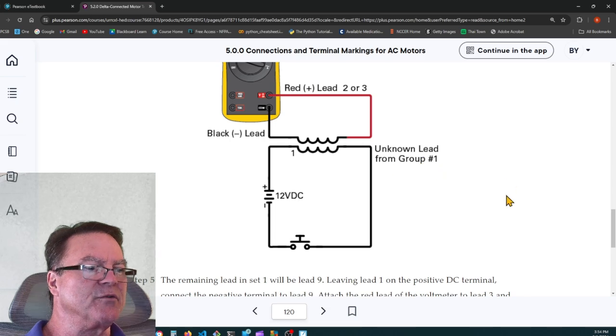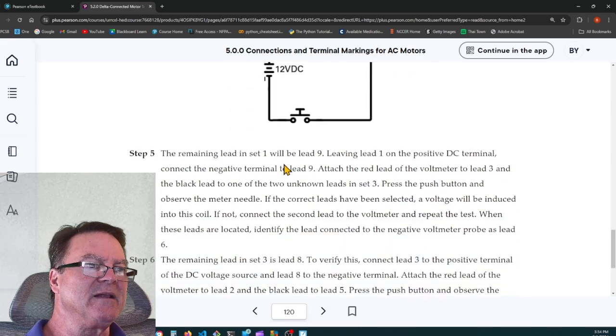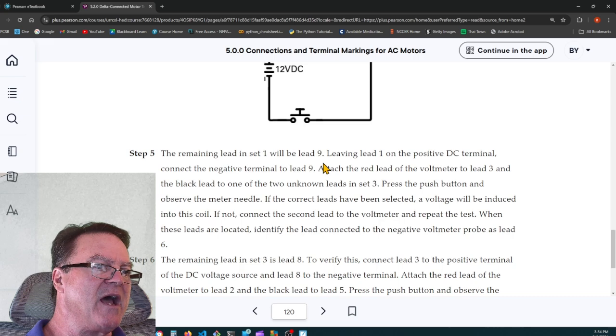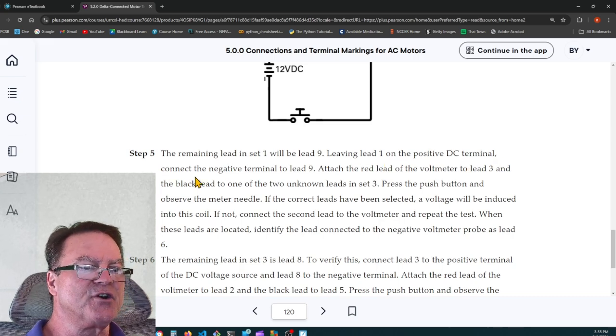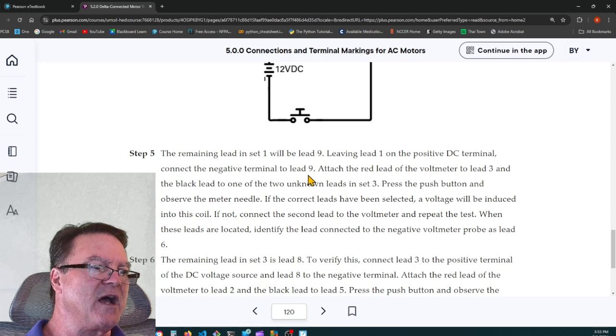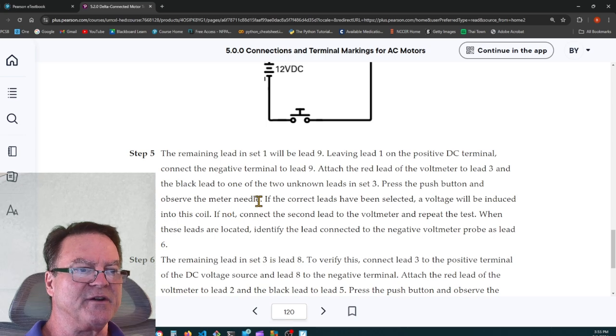This is the unknown lead for group 1. The remaining lead in set 1 will be lead 9, leaving lead 1 on the positive DC terminal. Connect the negative terminal to lead 9. Attach the red lead of the voltmeter to lead 3 and the black lead to one of the 2 unknown leads in set 3. Press the push button and observe the meter needle.